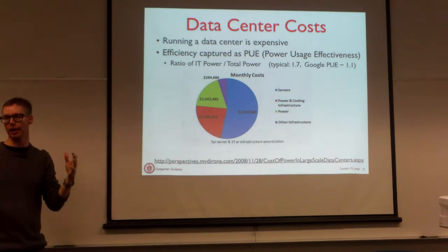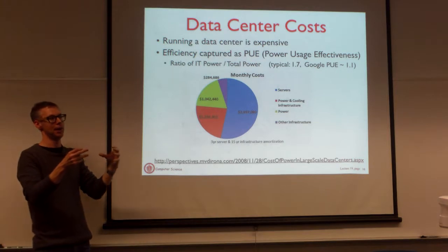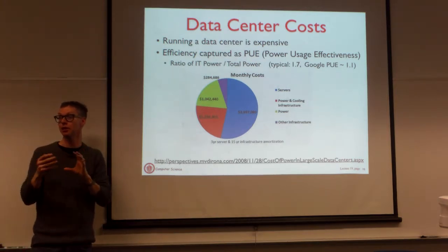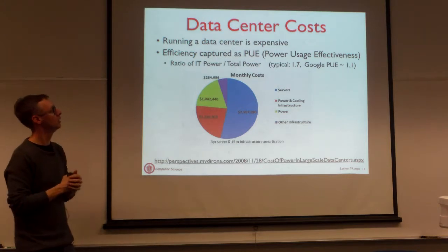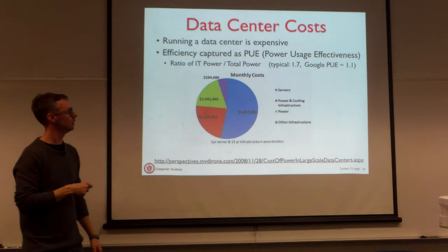So what that means is that 10%, basically you take the server power, you multiply by 10%, and the excess power to cool is roughly 10% of the server power. That's very efficient. In a normal data center, it's like 1 to 1 with the server.